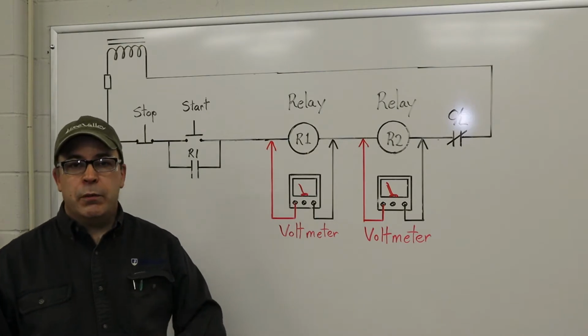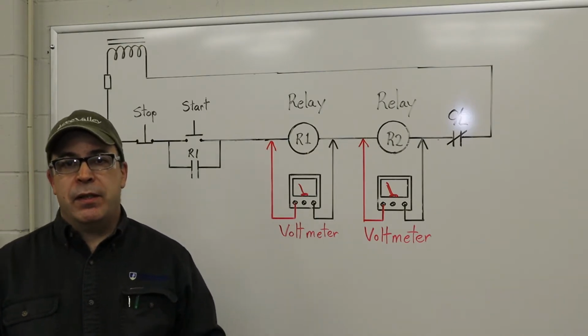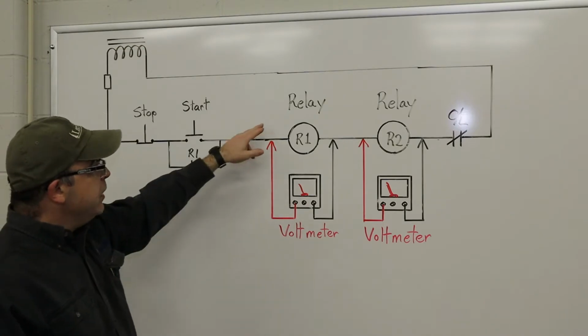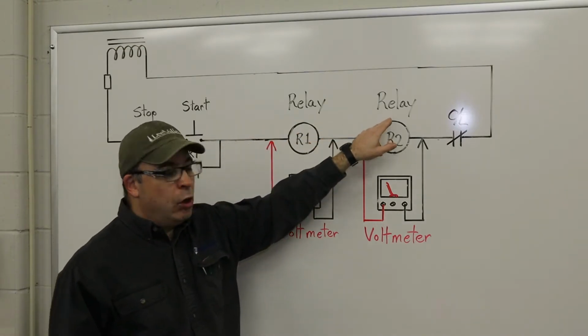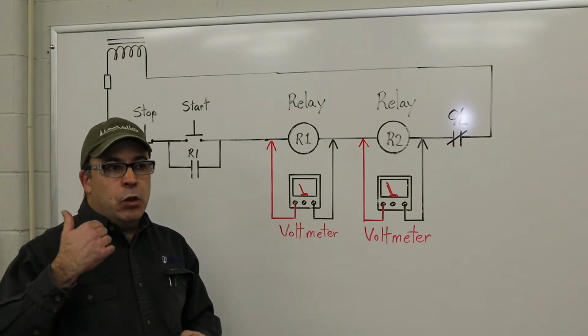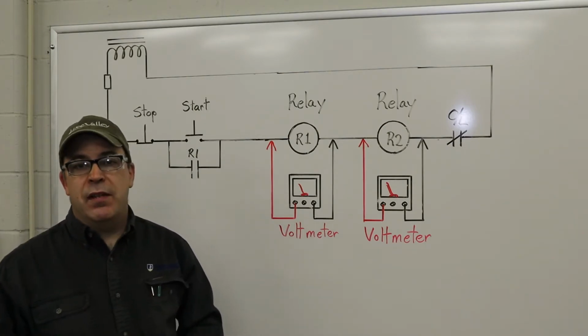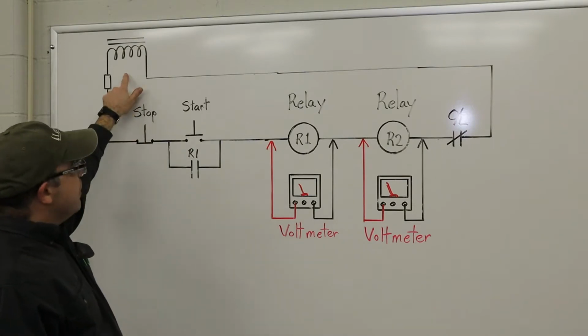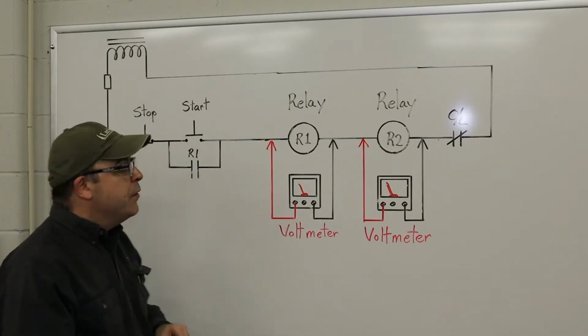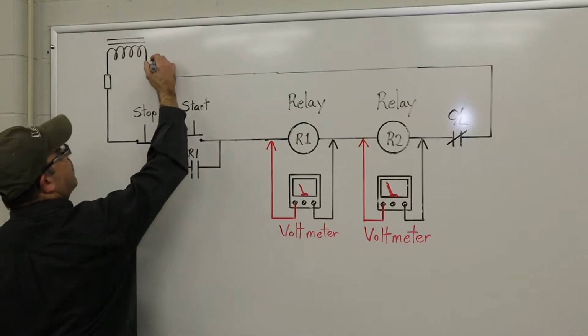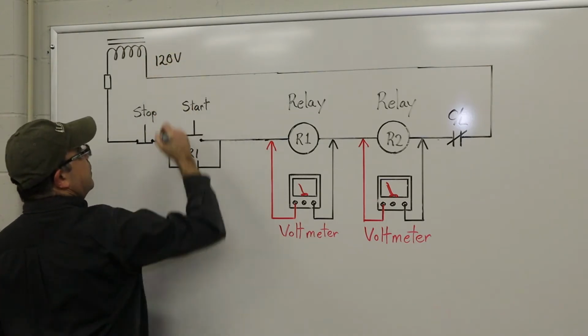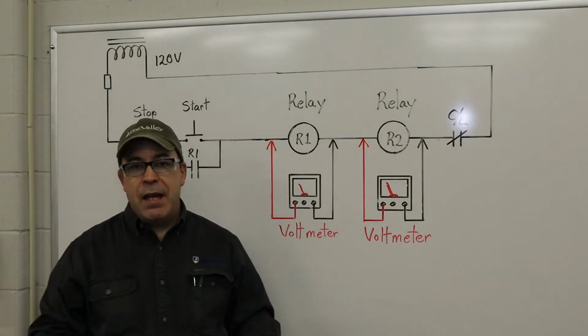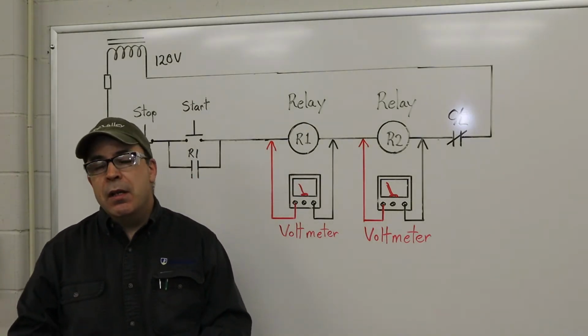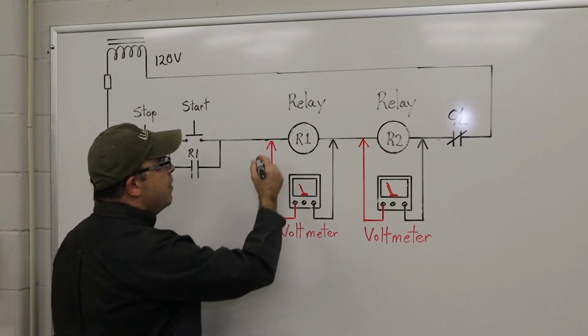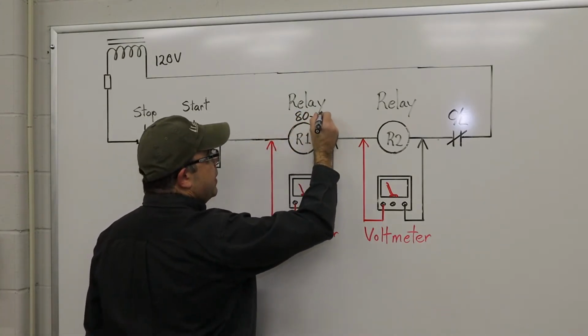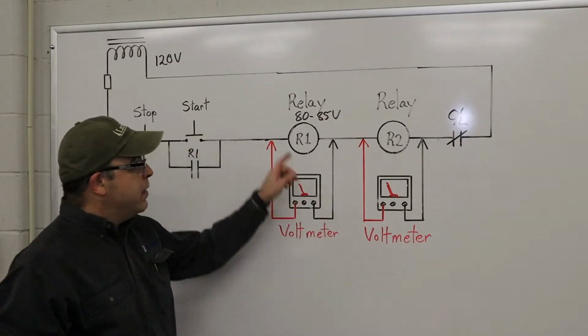one another. One of the reasons why we avoid a series circuit when it comes to motor control is that the voltage drop across each of these loads adds up to being lower than the applied voltage in the circuit. In this case, we have 120 volts on the control transformer. Now let's write that down. 120 volts. From our lab projects here at Cambrian College, my students will have discovered that it takes a minimum of 80 to 85 volts in order for this to function.